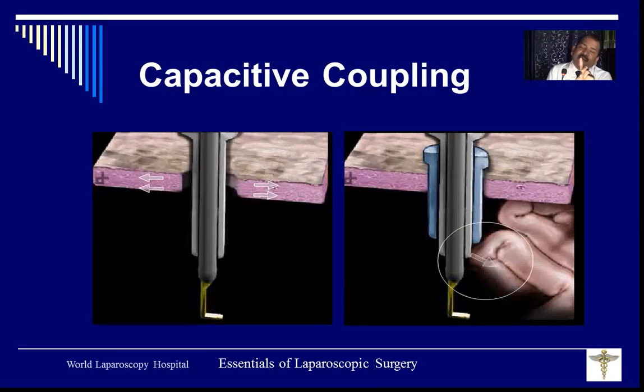Yes, every electrosurgical instrument radiates electromagnetic electrostatic waves. But if your reducer is made of metal, it will store and reserve that current like a capacitor. So does this only happen with a plastic cannula? Yes, it only happens if the plastic cannula is mixed with a metal reducer.